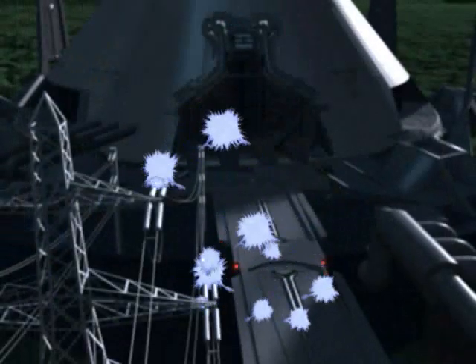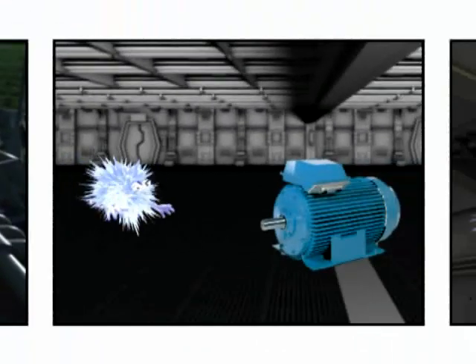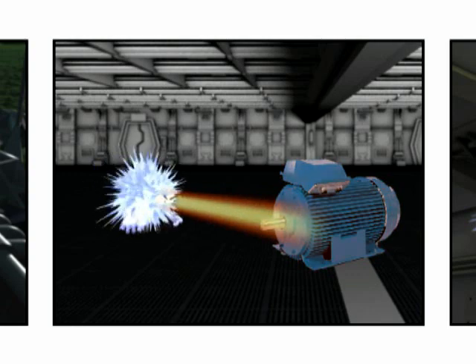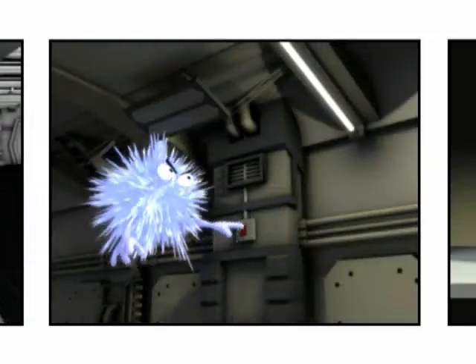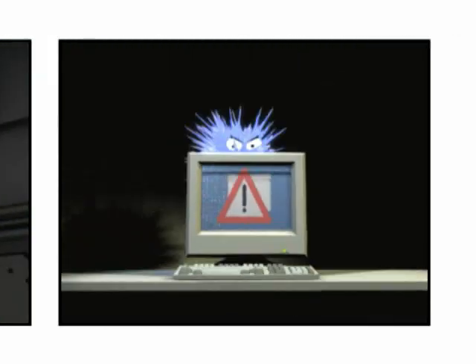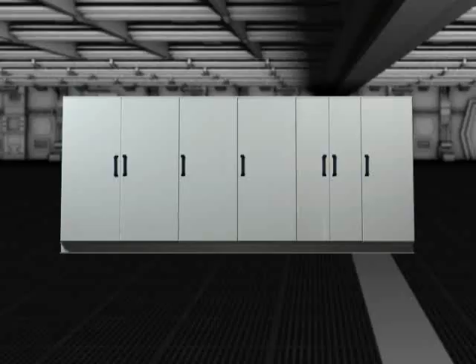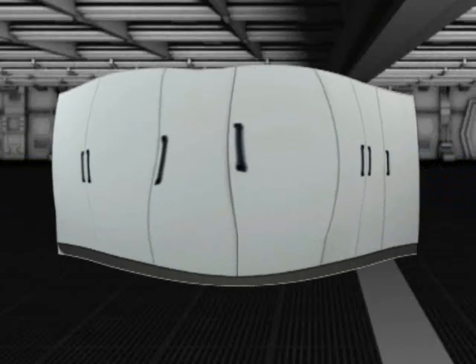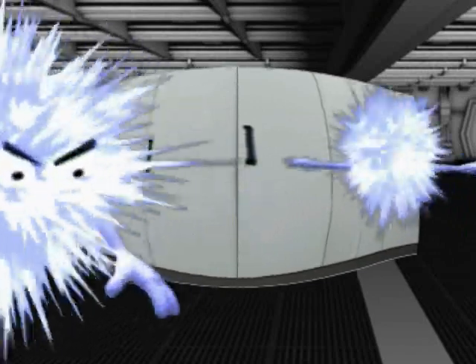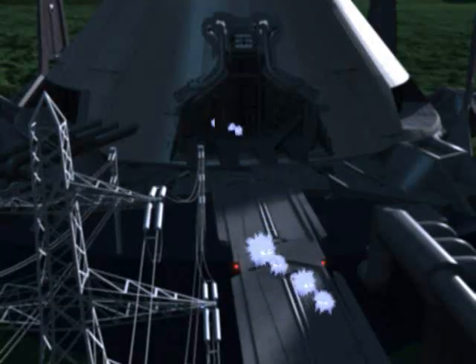You may not be able to see, smell or hear harmonics, but you can detect their trail of destruction — from excessive heating of conductors, motors or transformers, through to spurious tripping of circuit breakers, damage to lighting, and interference with communications equipment. And the problems don't end there. You may already have the enemy in your midst, as non-linear loads connected to the network, such as rectifiers and variable speed drives, are a breeding ground for more harmonics that can inject themselves directly into the grid.